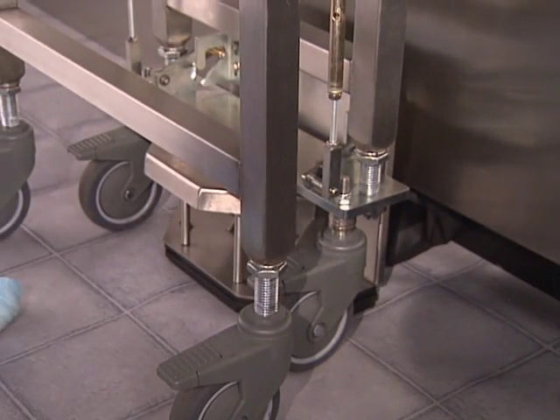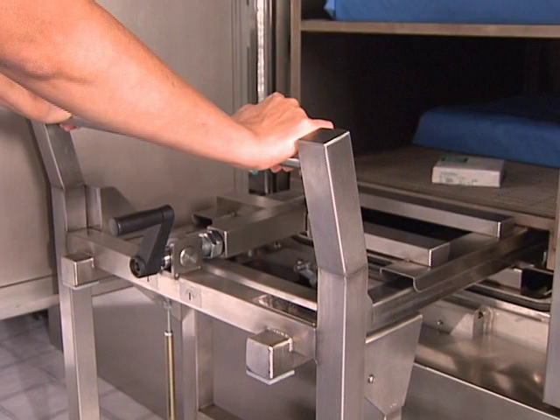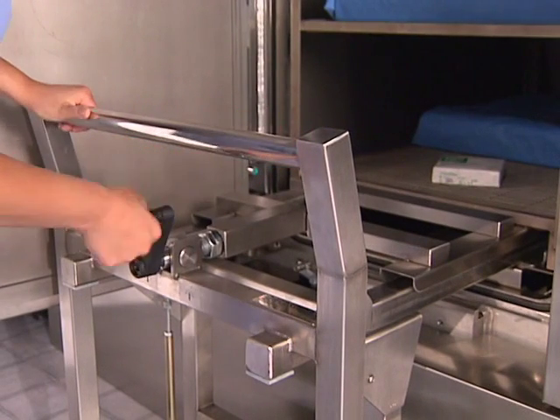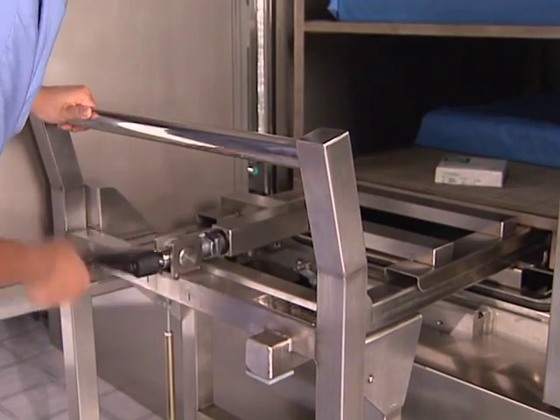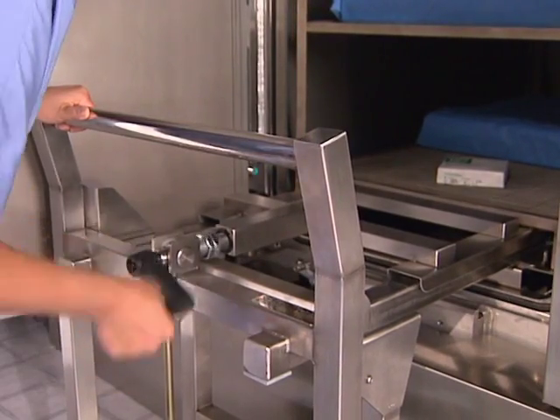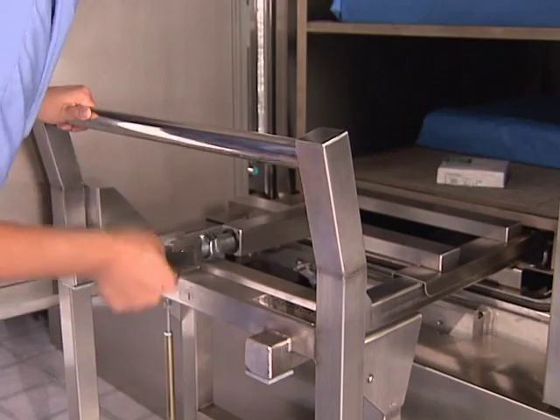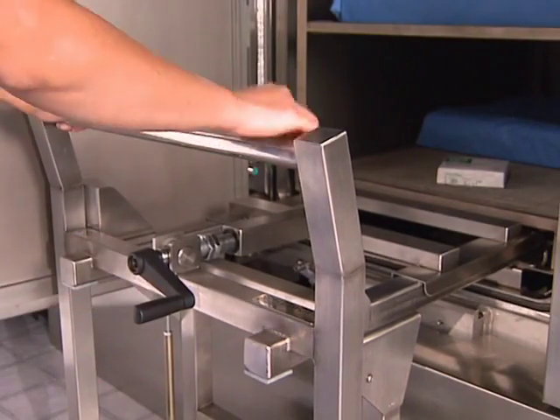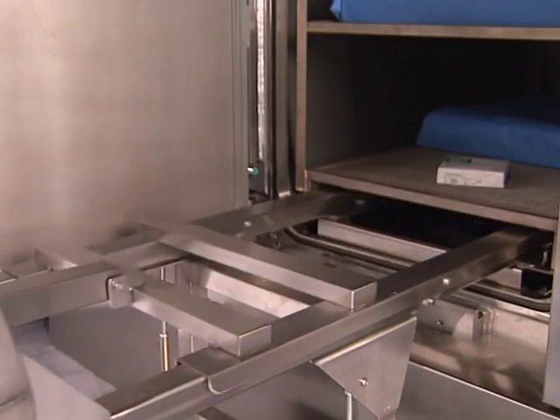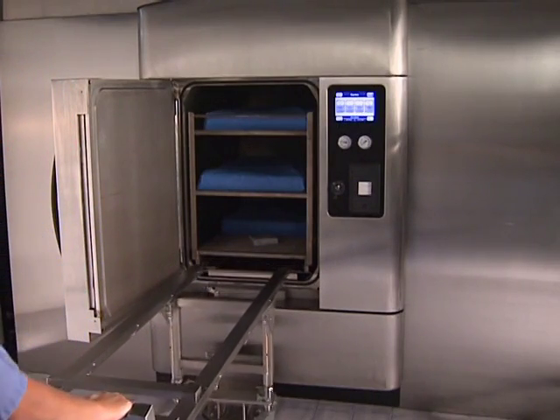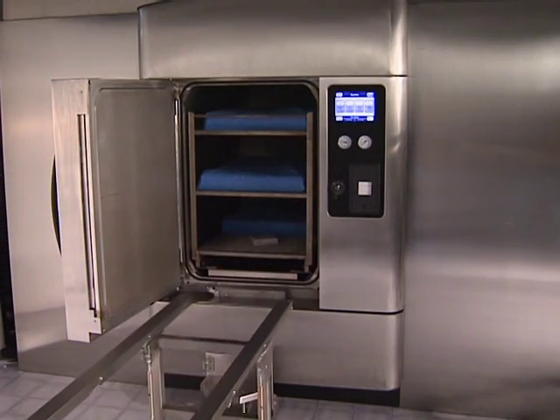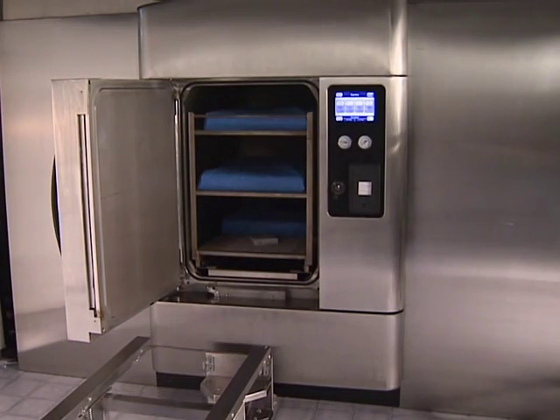Continue to press forward on the transfer carriage handle, fully inserting the loading car into the chamber. With the loading car fully inserted, turn the hand wheel counterclockwise until it stops, completely lowering the transfer carriage support arms and disengaging the loading car from the transfer carriage. Pull the transfer carriage away from the sterilizer chamber. The loading car will remain in the chamber during the cycle.